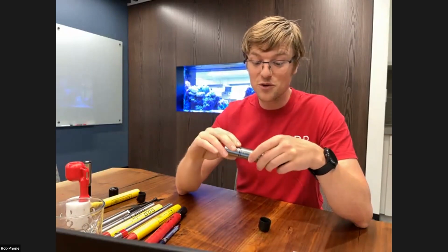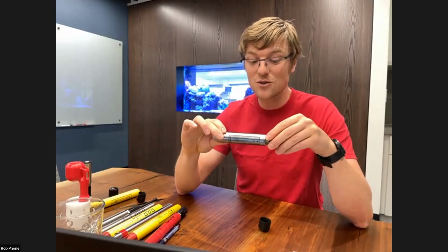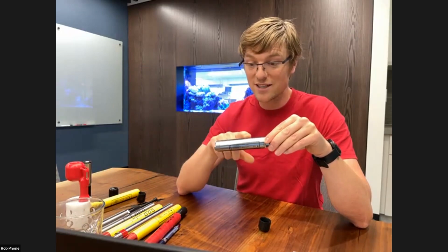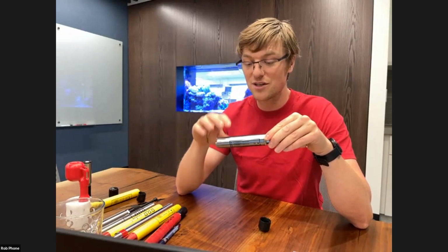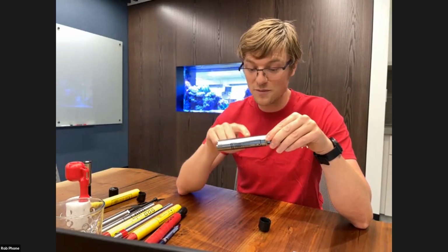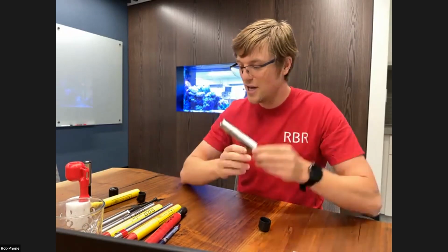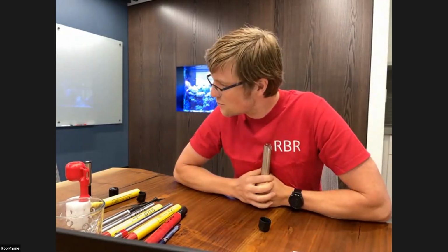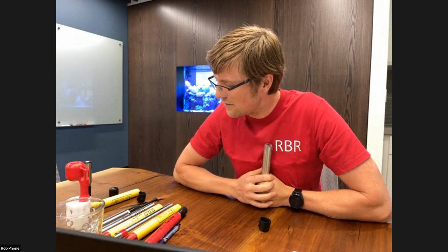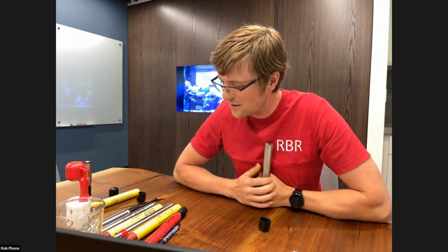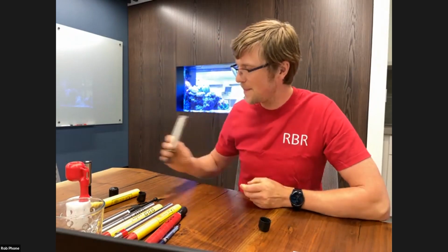And just like pressure, if you are just operating with the sensor standalone, you can input a static salinity value to do the compensation on board from the output of the sensor. Other sensors, I don't believe, have a strong dependence on salinity. Yeah, I think it's just that optode.